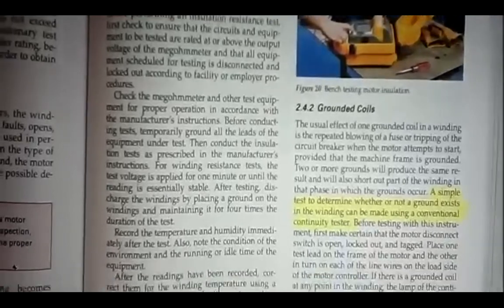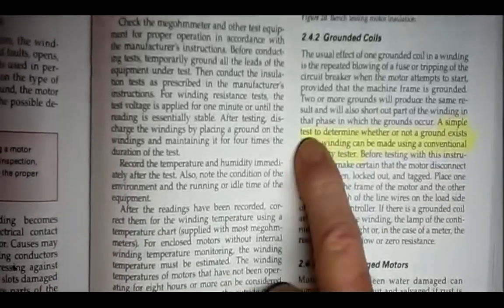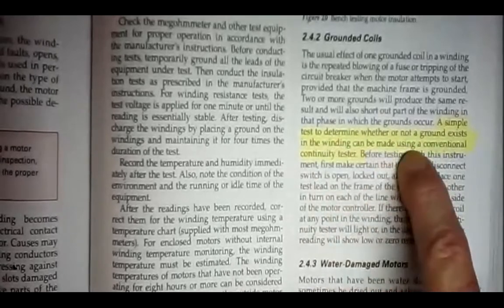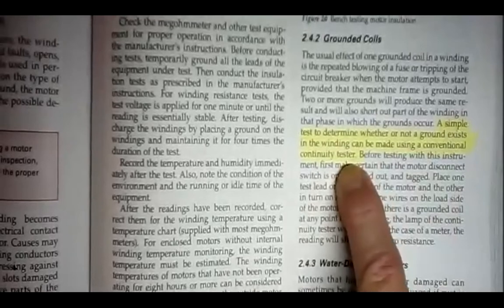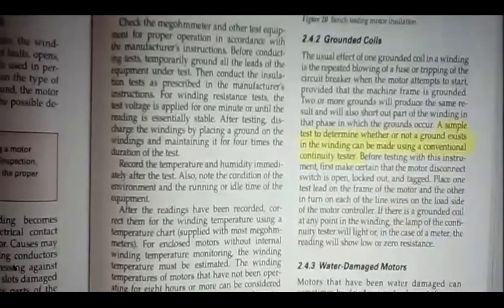Grounded coils. On page 23 on the right-hand column, grounded coils. A simple test to determine whether or not a ground exists in the windings can be made using a conventional continuity tester. So, just go from the windings to the frame of the motor and see if you get continuity.